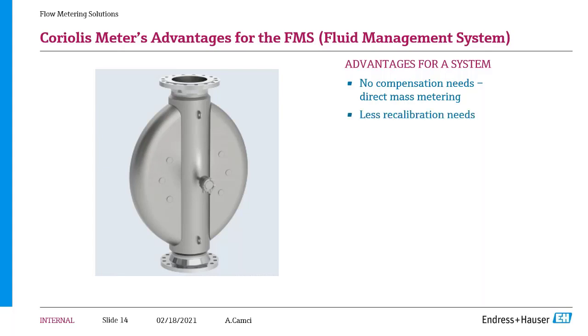The meter doesn't have any moving parts inside, so there is no wear and tear inside the meter. It needs less recalibration and less maintenance, therefore it gives a higher availability. It does the job it is supposed to do for longer times. There are no shutdowns for maintenance and such. The meter is easy to install. It can even hold on the piping without supports. It has a compact footprint for ease of installation.